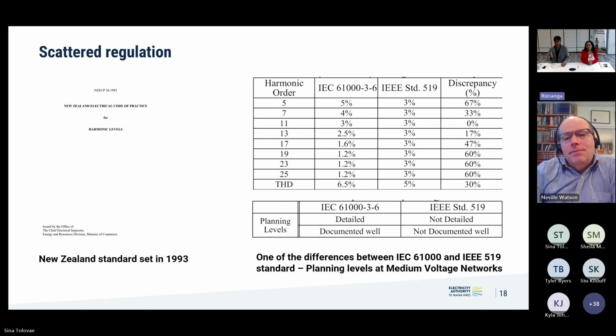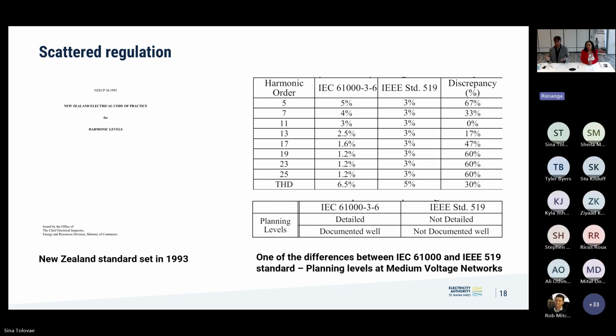You can see there's a discrepancy. If a utility uses IEEE 519 and the neighboring utility uses 61000, there's already a discrepancy in the harmonic order. So as a solar farm connects to one utility, they might face a different set of regulations than at another. We do have scattered regulation, so we are trying to bring the whole system under a single umbrella now.